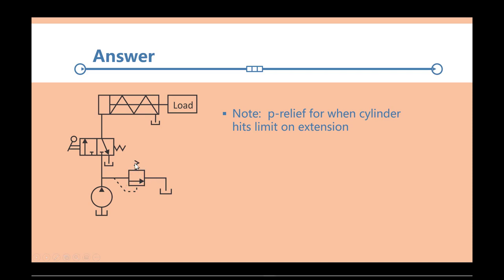It has a spring bias on it. So as you can see, the spring is pushing on it and makes it so fluid can't flow through it. But if the pressure builds upstream of the valve, then that will push the envelope or push the valve upwards so that the flow path is then provided to go from the pump to the tank.